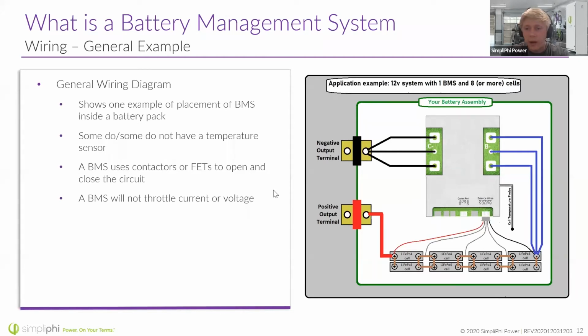Many BMSs do have cell temperature probes, some do not. Note that they use some sort of device to open or close the circuit on the negative end. If it sees something it doesn't like outside its parameters, it opens the circuit. If everything's good, it closes the circuit. The BMS is not going to throttle or modify the current or voltage being provided to the battery, it's just going to open or close the circuit.